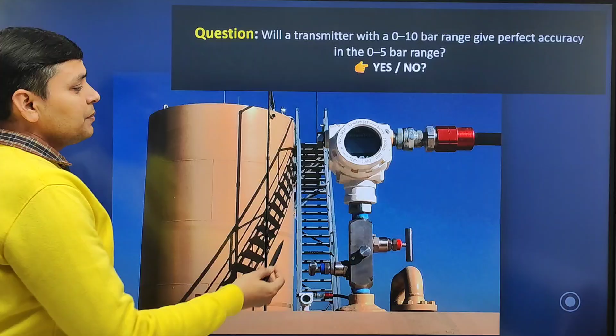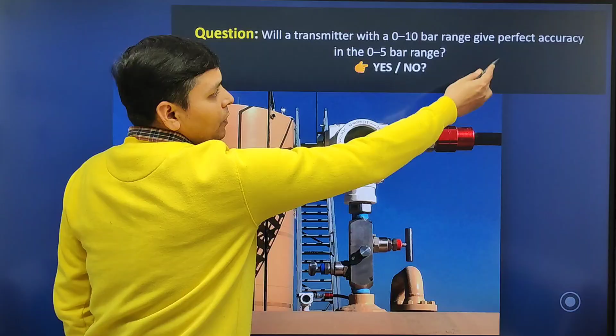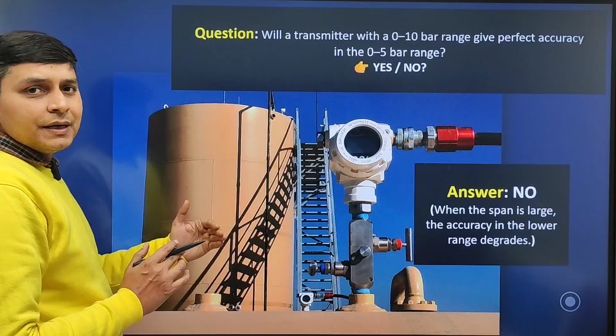The first question is, will a transmitter with a 0 to 10 bar range give perfect accuracy in 0 to 5 bar range? Suppose we are using a pressure transmitter, and if we reduce its range from 0 to 10 bar to 0 to 5 bar, what will be the effect on its accuracy? Its accuracy will be same or it will degrade. So its answer is, it will not give the perfect accuracy if the range is decreased. And the reason behind this, the accuracy in the lower range degrades. So if we are using any transmitter and if we degrade its range, then its accuracy will also degrade.